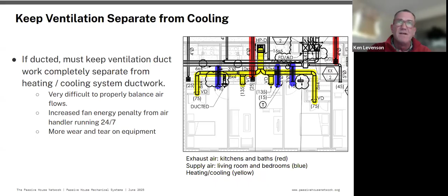The problem is the heating and cooling system needs to run at much higher fan power, with bigger ducts and bigger flows, while the ventilation system is very low flow and low fan power. It's apples and oranges. So the basic approach is to keep these things separate—if you combine them, you introduce a whole set of variables and complications, balancing becomes very difficult, there can be a substantial energy penalty, and more wear and tear on the equipment. So again, passive house pushes towards simplicity in what we're trying to do.